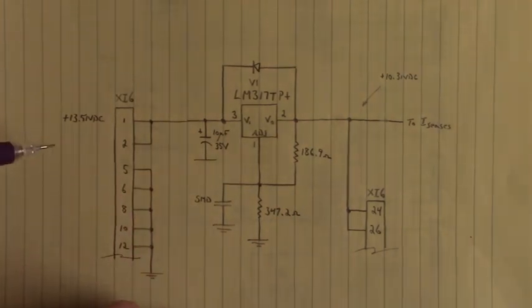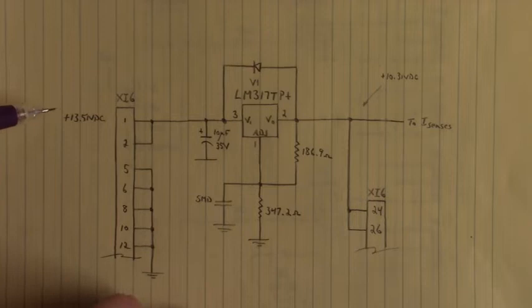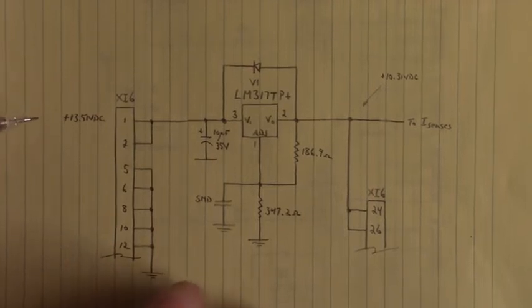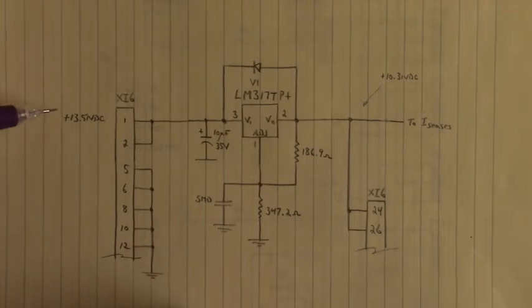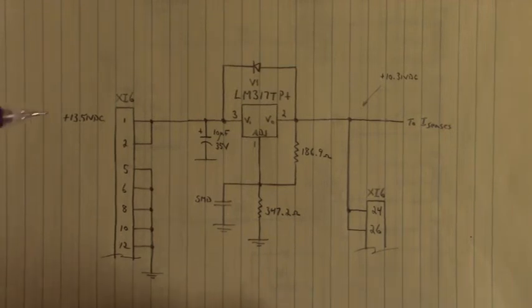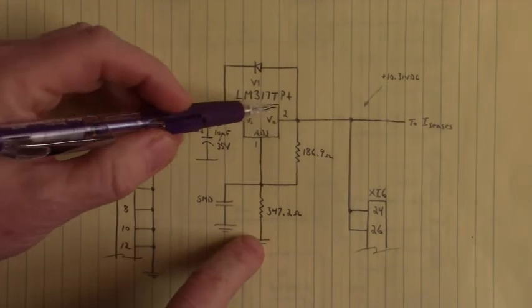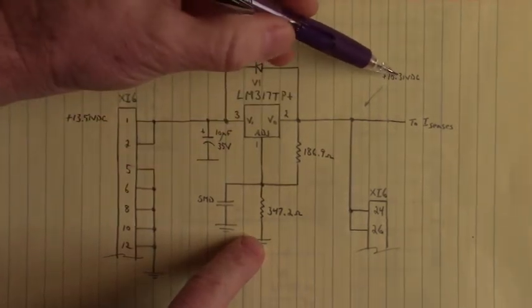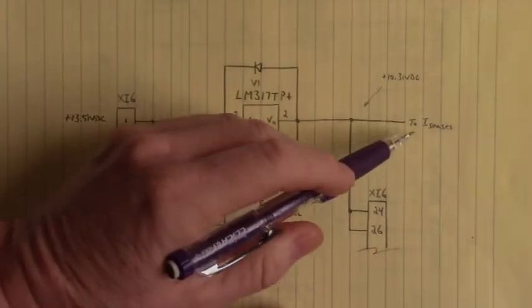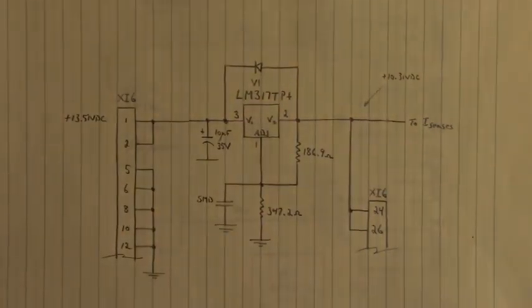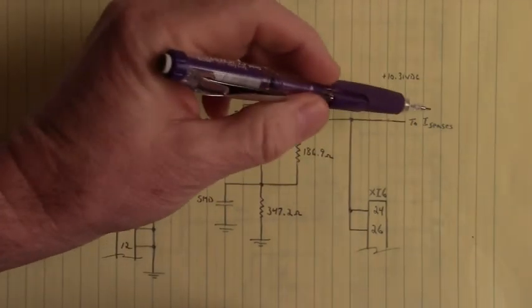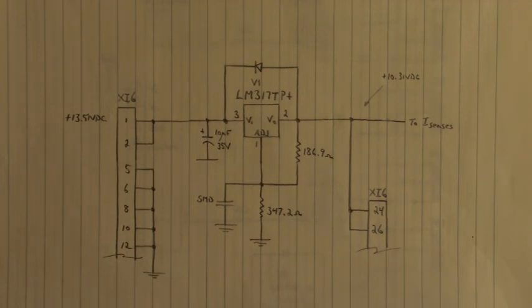And it takes 13... Are we still in the board? Are we still in the camera here? I got papers going this way and that way. It takes 13.51 volts DC in from that full bridge rectifier back there, and makes plus 10.31 volts DC. I measured it to power up the current sense modules. Now that is how Alarm 71 is related, from no volts on the current sense modules back to that bad switching circuit that we repaired.